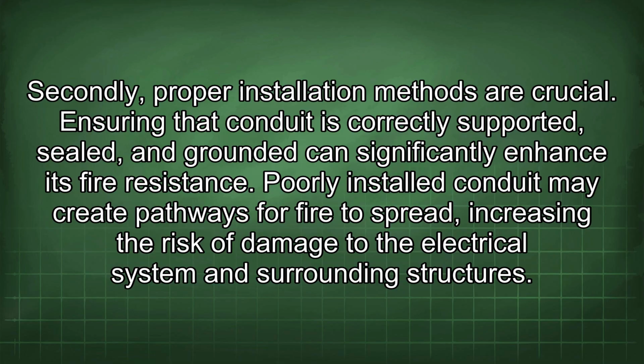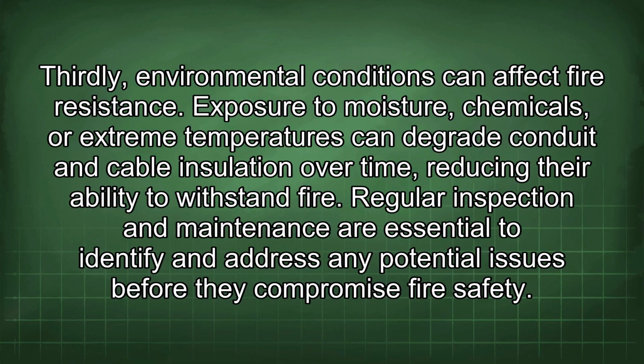Secondly, proper installation methods are crucial. Ensuring that conduit is correctly supported, sealed, and grounded can significantly enhance its fire resistance. Poorly installed conduit may create pathways for fire to spread, increasing the risk of damage to the electrical system and surrounding structures. Thirdly, environmental conditions can affect fire resistance. Exposure to moisture, chemicals, or extreme temperatures can degrade conduit and cable insulation over time, reducing their ability to withstand fire. Regular inspection and maintenance are essential to identify and address any potential issues before they compromise fire safety.